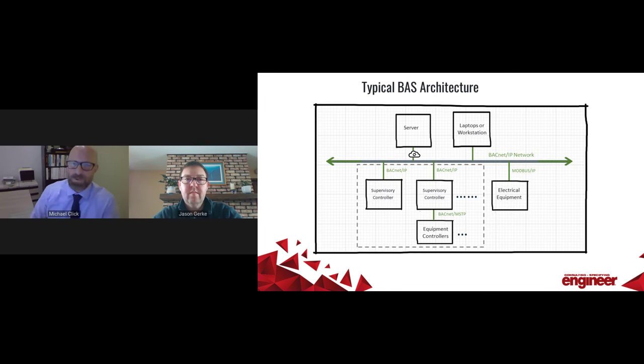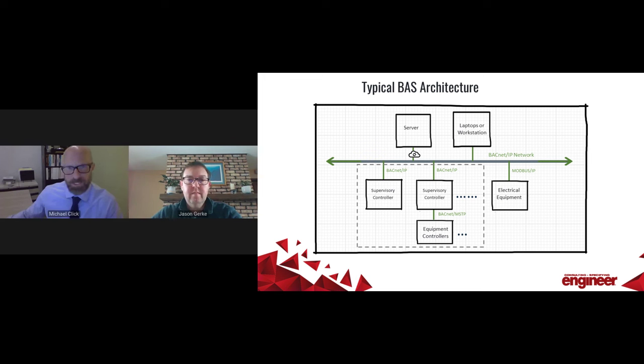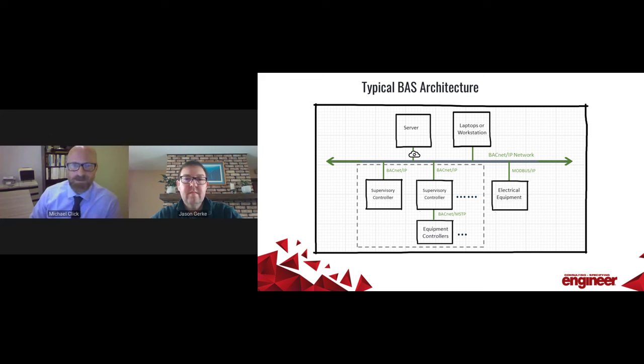The next slide shows something we see quite a bit in the industry, where you have one protocol bus with another protocol bus tied into it. You see the same application layers: the server application layer at the top with the server and workstations, and the supervisory controller layer below. A lot of times in our projects, we see electrical equipment tied into the BACnet bus through Modbus. So it's not uncommon to see two protocols operating one control system.